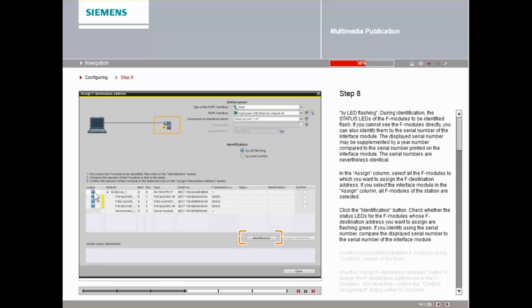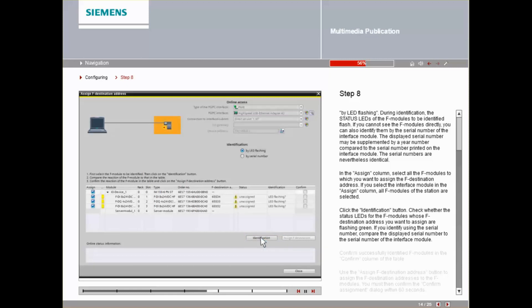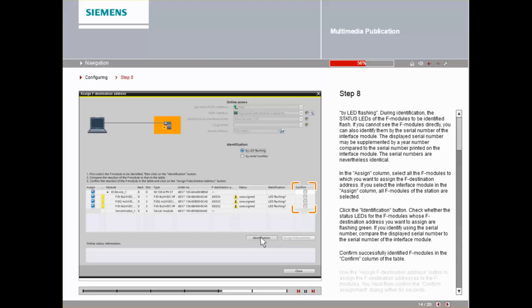Check whether the status LEDs for the F-Modules whose F-Destination address you want to assign are flashing green. If you identify using the serial number, compare the displayed serial number to the serial number of the interface module. Confirm successfully identified F-Modules in the Confirm column of the table.